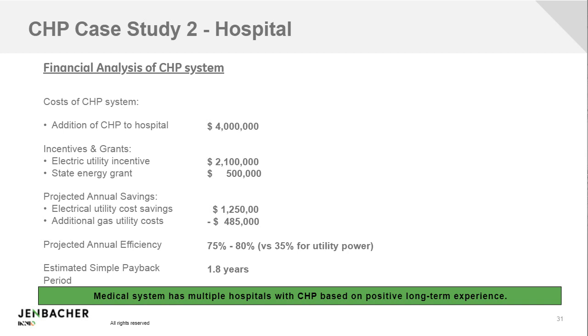Annual savings broken down: electrical utility cost savings of $1.25 million. Yes, they are using a little bit more gas, so they're using $485,000 worth of additional gas. Using a conservative estimate of 75 to 80% total CHP system efficiency versus 35% for utility power, they're expecting to realize a simple payback period of 1.8 years. That's a pretty quick payback period for a $4 million system.